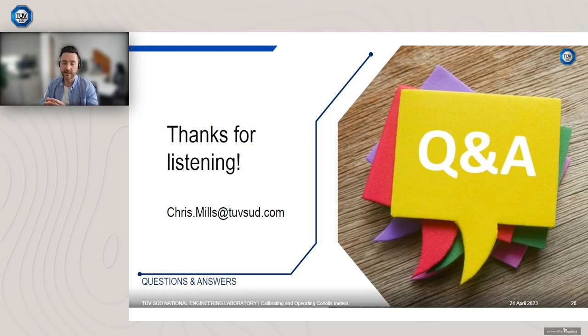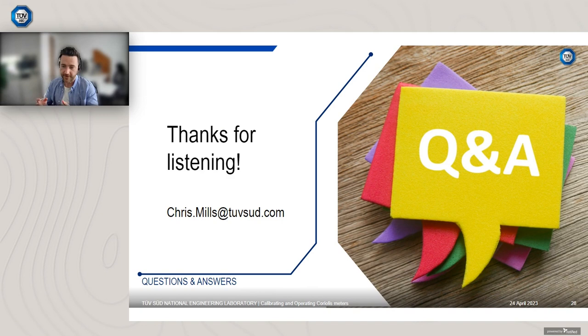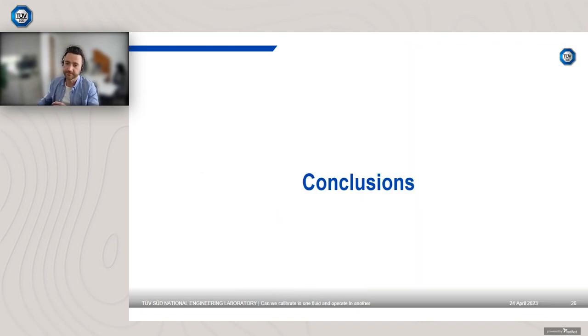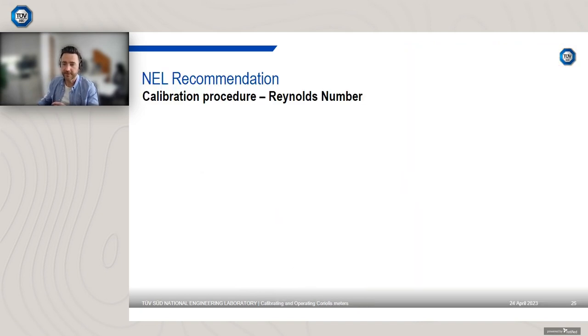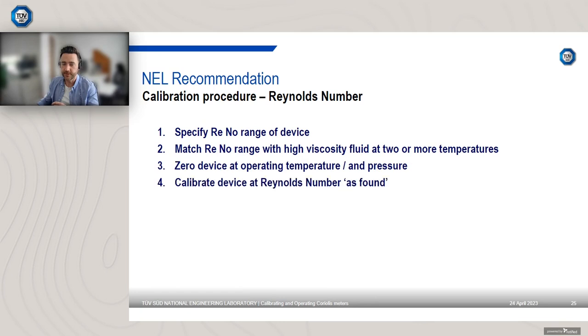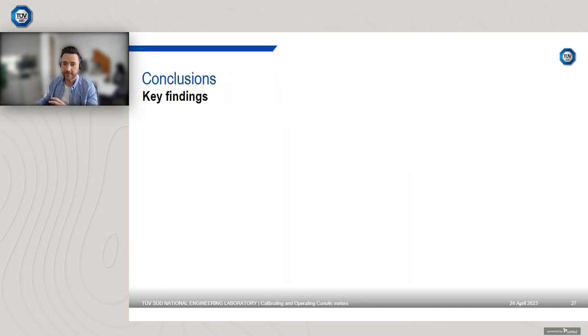We find that the temperature affects a magnitude less than pressure because of the onboard temperature measurement from the device. We find that Coriolis meters should be characterised against Reynolds number if the fluid is high viscosity. And then, apologies again, my slides have moved forward. Just going to move back. And then, that's the wrong slide, right there.